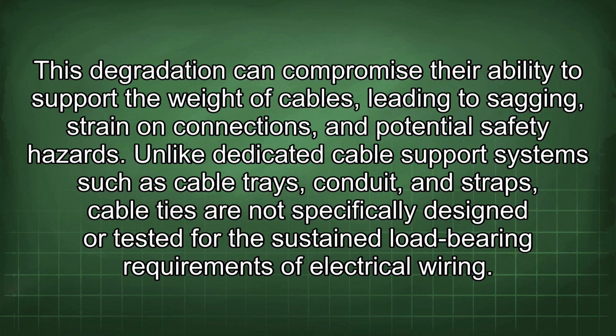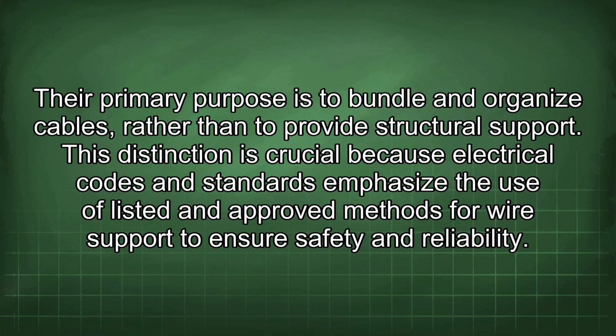Unlike dedicated cable support systems such as cable trays, conduit, and straps, cable ties are not specifically designed or tested for the sustained load-bearing requirements of electrical wiring. Their primary purpose is to bundle and organize cables, rather than to provide structural support. This distinction is crucial because electrical codes and standards emphasize the use of listed and approved methods for wire support to ensure safety and reliability.